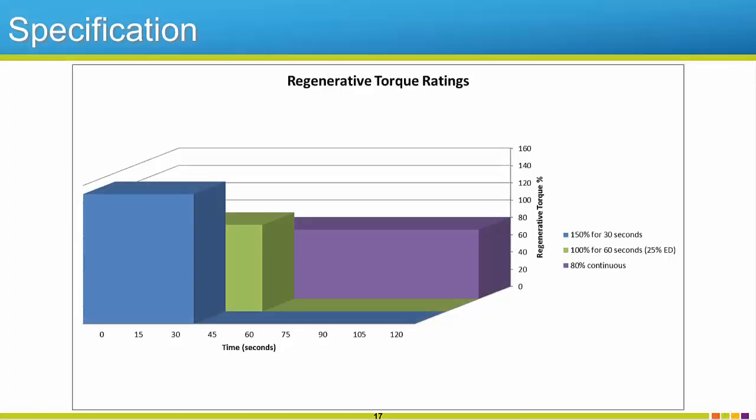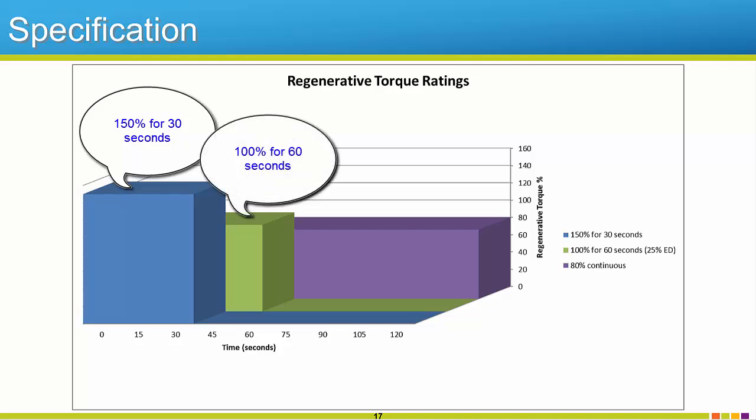While we are on the topic of duty ratings, here's some performance ratings for the R1000. The R1000 can handle up to 150% regenerative torque for 30 seconds, 100% for 60 seconds, and 80% regenerative torque continuously. Notice how at 100% regenerative torque, the duty cycle must be 25% or less. To simplify what that means, we can think of an application that regens 25% of the time. For example, one minute on and three minutes off. During that one minute, the R1000 can handle 100% regenerative torque.